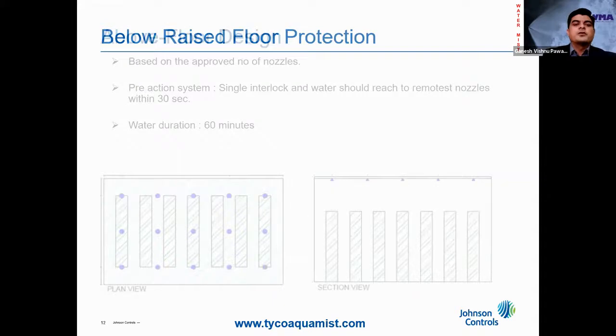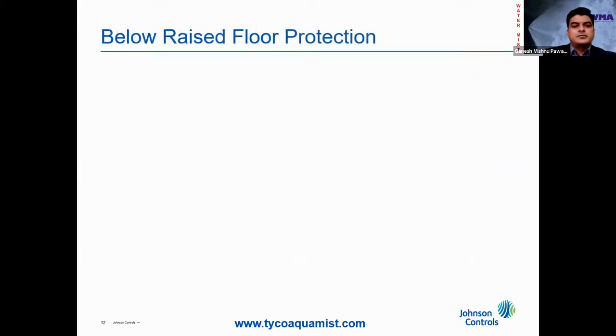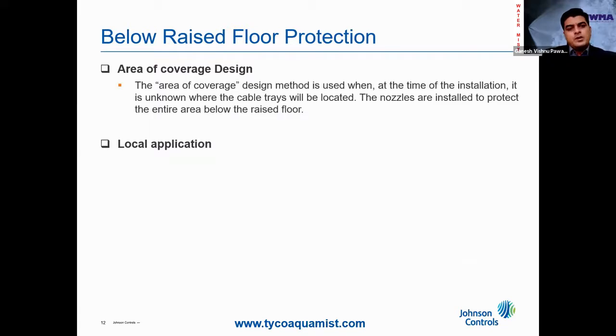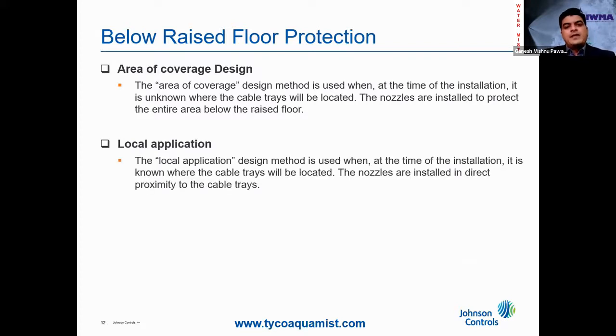When we talk about the protection for the below raised floor, it can be achieved either by area of coverage design or by a local application. When at the time of installation we know exactly where the cable trays will be located, the local application is used and the nozzles will be installed in proximity to the cable trays in a linear fashion. Whereas if at the time of installation we don't know the exact location of the cable trays, then nozzles are installed to protect the entire area below the raised floor.